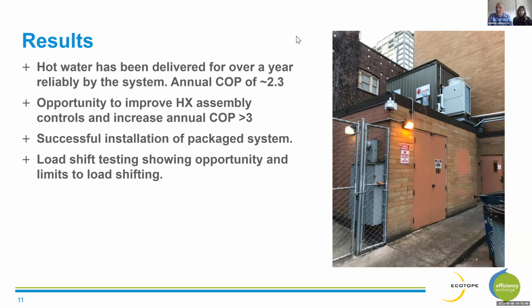We're not getting quite as good of a system COP as we were targeting. We're getting about a 2.3, although we've identified ways that Mitsubishi can improve the control of their heat exchanger assembly to get closer to that target COP of 3. We demonstrated a successful installation of a fully packaged system, and we've shown the opportunities for load shifting and what we can get out of that. Madison will show more details of that.